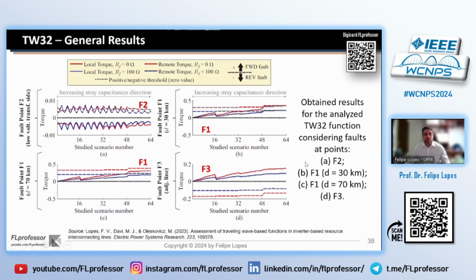And now, just to go to the ending part of my presentation, this is a sensitivity analysis that we carried out just to see what to expect from these functions by varying these stray capacitances. Regarding the directional element, when we consider external faults behind the transformer on the IBR side, we can see that there is a behavior which is reliable because the elements properly see the direction of the short circuit on both sides. But for internal faults and for faults beyond the remote terminal where the grid is connected, we can see that there is a trend of reducing the amplitudes of the protection element torque, which shows that for small stray capacitances, we may have some problems here.